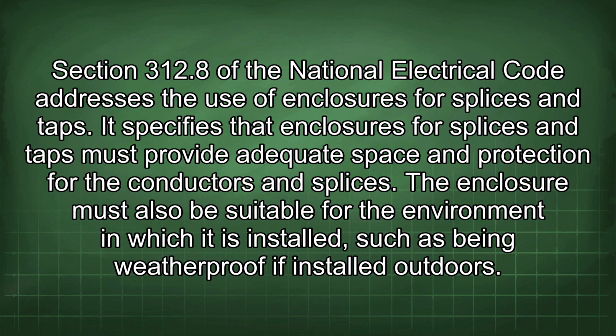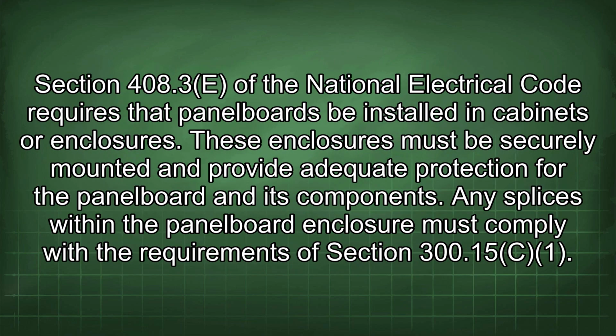Section 312.8 of the National Electrical Code addresses the use of enclosures for splices and taps. It specifies that enclosures for splices and taps must provide adequate space and protection for the conductors and splices. The enclosure must also be suitable for the environment in which it is installed, such as being weatherproof if installed outdoors.